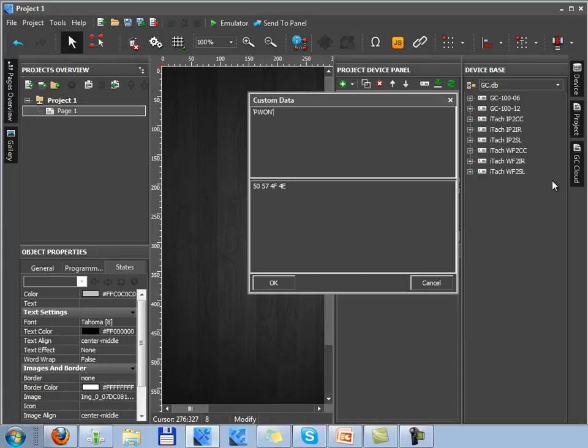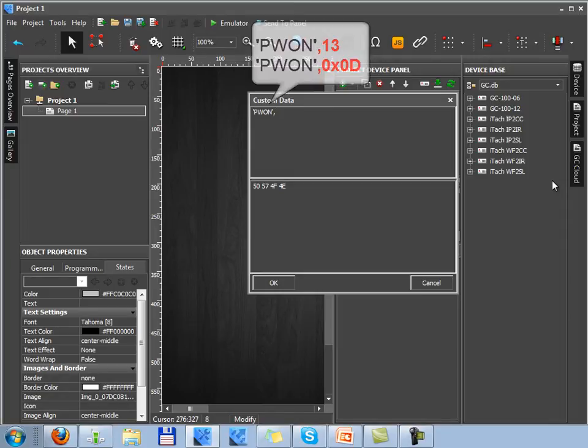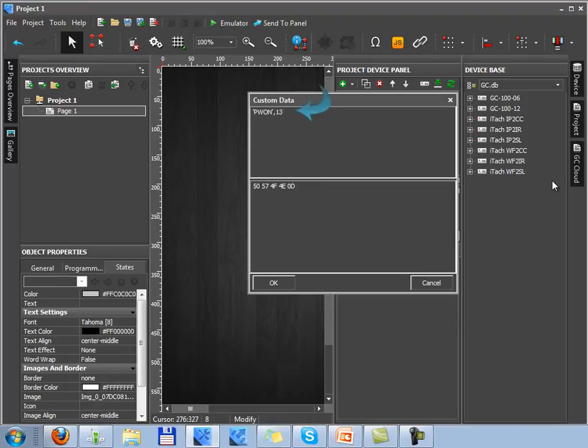But we also need when working with COM ports using RS-232 the end of string symbol. The end of string symbol is the hex code and it is 0x0d or comma 13. This code must be written after closing the string of the ASCII format. Otherwise COM port of the control equipment will not understand the command correctly and it will wait for its resuming as the command can include a great number of symbols.